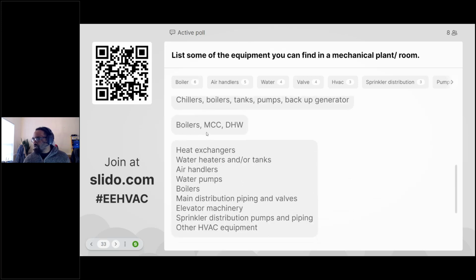All great answers. Boilers, very important. I noticed someone put here an MCC, and that is a really good catch. The MCC, the Motor Control Center, you will find located on both the electrical side of the house and the mechanical side, because your pumping systems, which contain motors, are going to be located on this MCC panel. Depending upon the size of the facility and the mechanical room, I've seen up to 20 pumps in a mechanical room. So you'd have an MCC control panel with 20 different areas where you have control for each pumping system.